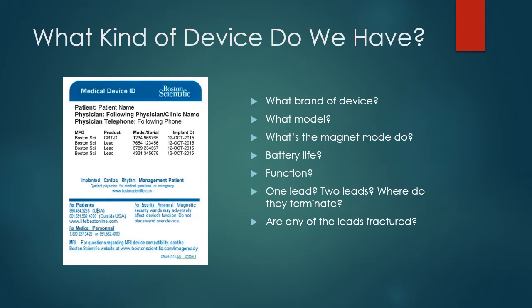You should know what happens if you put a magnet on the device because you're afraid of interference from what the surgeon is doing. You can x-ray these devices. If the person doesn't know and they don't have their card — most people have a card — you can ask to see it. You can call Boston Scientific or Medtronic and find out exactly what they have and when it was last interrogated. Medtronic is now getting stations out to hospitals that can interrogate the pacemaker with little interference, and you can talk to the reps or engineers who can remotely access the device, change things, and change it back after the case.